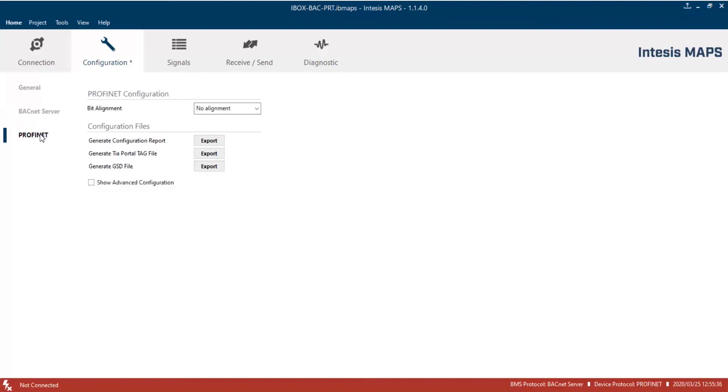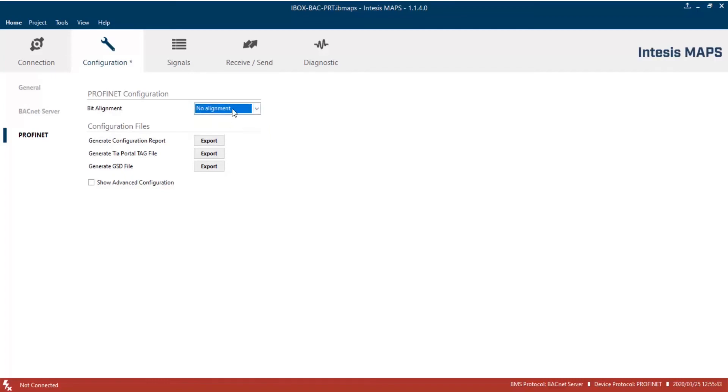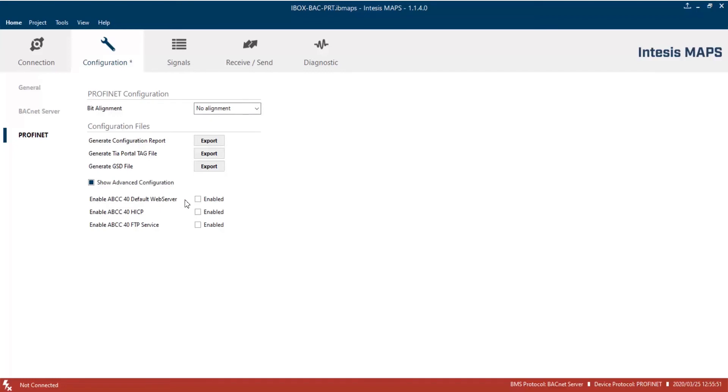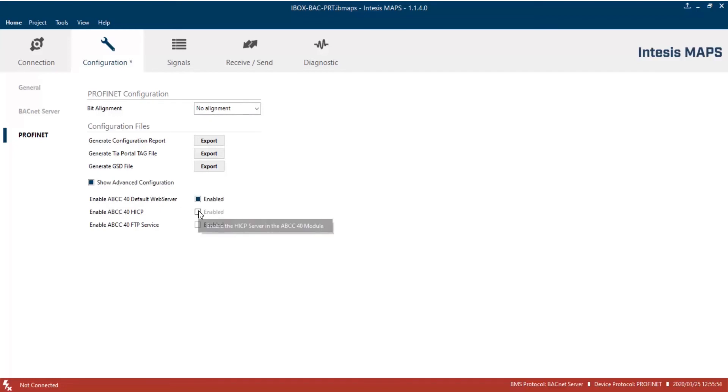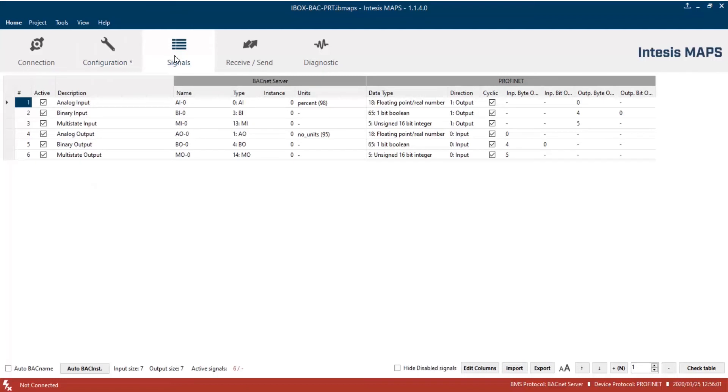Now, let's move to the Profinet tab. Here, set bit alignment in the input-output structures. And then, on the Advanced Configuration, we'll enable default web server and HICP communication in the Profinet interface. They will help us on commissioning process. Once process finished, we recommend to disable them again, for security purposes.